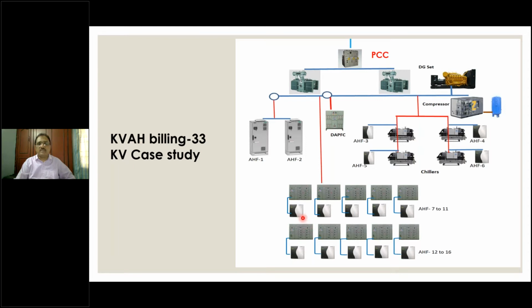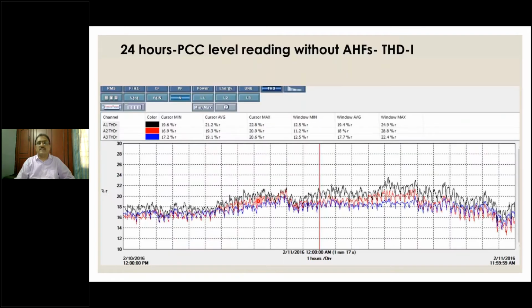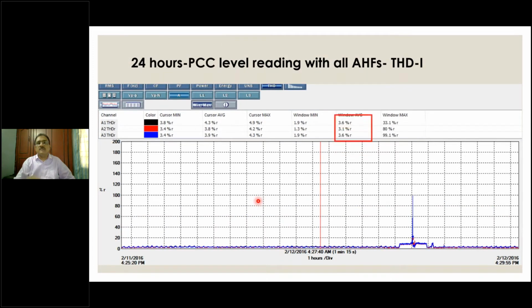So then we designed active harmonic filters for 10 of the MCCs, one each 60 ampere for the chillers, because these are also 6 drives. And then overall 2 numbers of 300 ampere active harmonic filters. This was required, warranted, without which we would not have been able to bring this kind of result. From something like 19%, we brought it down to less than 4%.